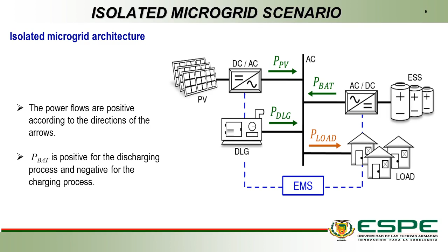Here we can see the block diagram of the proposed fuzzy-based energy management system that comprises 5 blocks. With these blocks, we provide the reference values of the photovoltaic generator, diesel generator, battery energy storage system, and the diesel generator status indicator. Block 1 consists of a moving average filter in charge of computing the average of the forecast generation and load data, to have prior knowledge of the amount of photovoltaic power that the system could use to cover the demand.